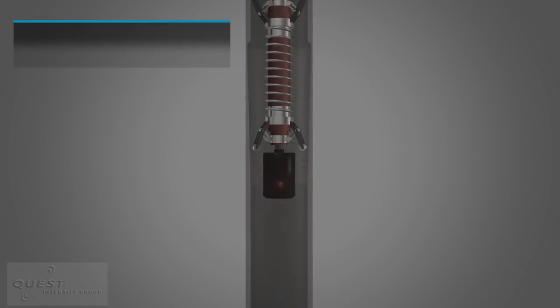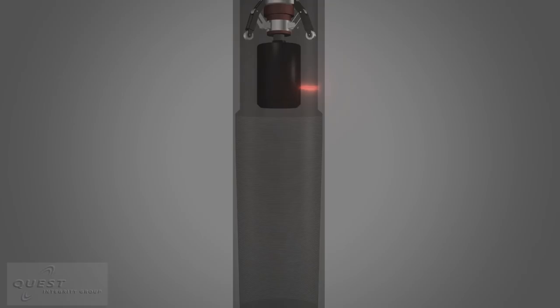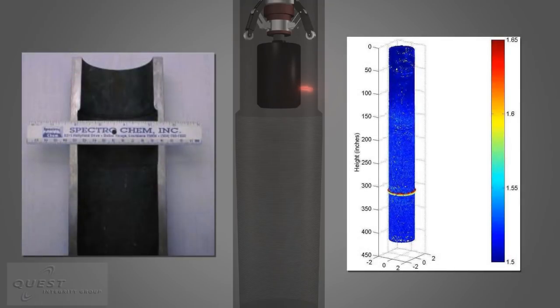LOTUS detects an internal manufacturing gouge inadvertently caused by the manufacturer. Gouges on the tube's internal surface can generate localized stress risers, causing premature cracking.